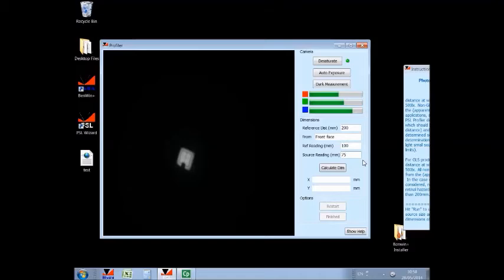With this information, we can hit calculate dimensions, and a Hull algorithm will look within the full image for the maximum signal, calculate 50% of that, and this blue band will come in from all angles to fit around the image, the maximum dimensions at 50%. And finally, 2 orthogonal dimensions will be taken, which are reported here as 3.01 and 2.97 millimeters.